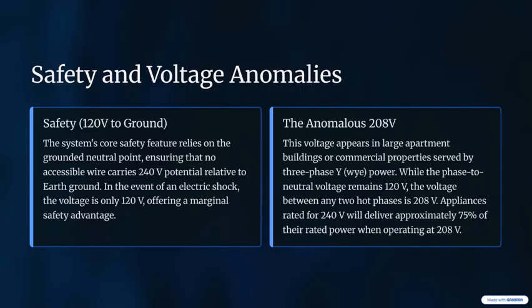And the impact of that compromise is substantial. An appliance that's rated for the true 240-volt standard, which is common for commercial ovens or HVAC units, will deliver only approximately 75% of its rated power when it's connected to that 208 feed. You can see this in slow-running resistive heaters. This mathematical necessity of maintaining 120 to neutral forces an operational compromise on higher power equipment.